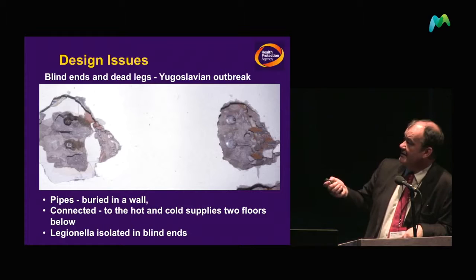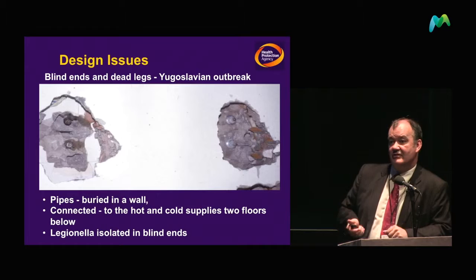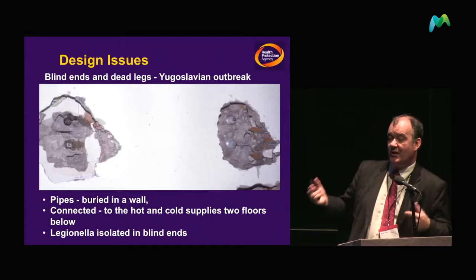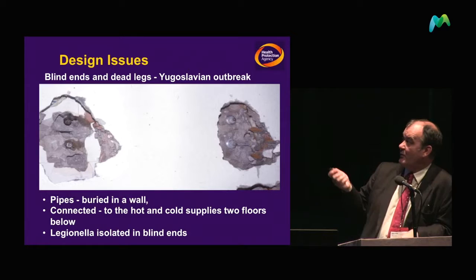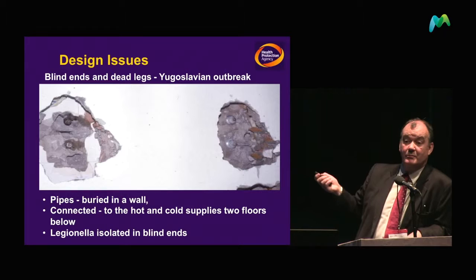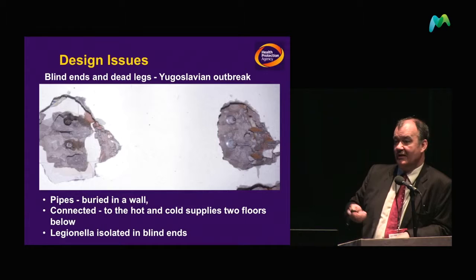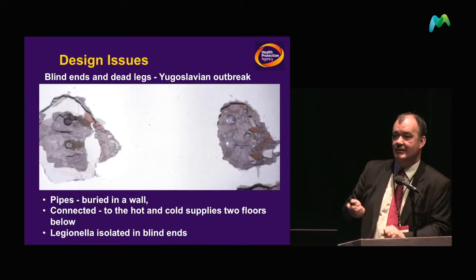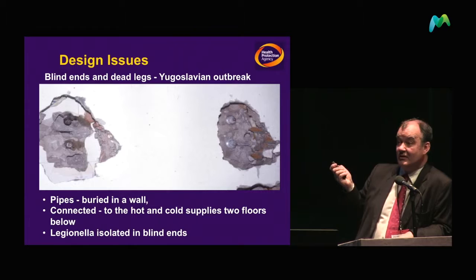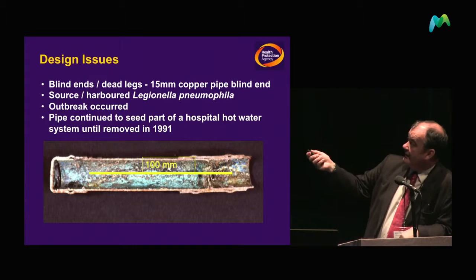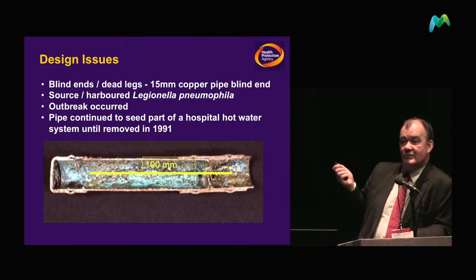This was taken from a Yugoslav hospital outbreak — pipes that were actually buried in the wall. Despite all the efforts of the hospital to find the cause, they could not find it, but by progressive sampling were able to narrow it down to one section. At that point they decided to go into the wall and found blind ends — someone had at some point revised the plumbing and instead of capping it off properly just left the end.